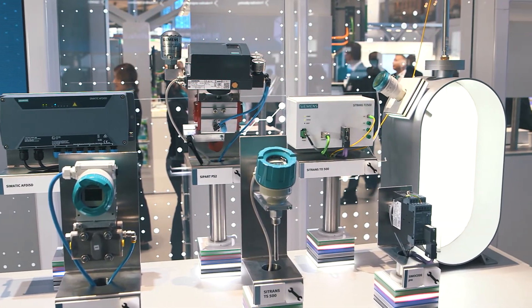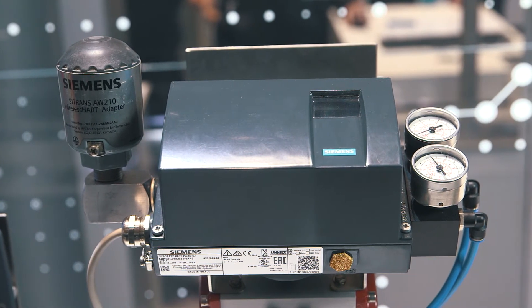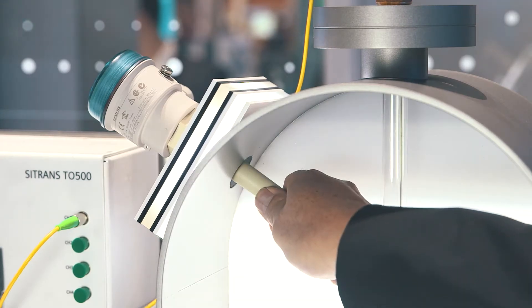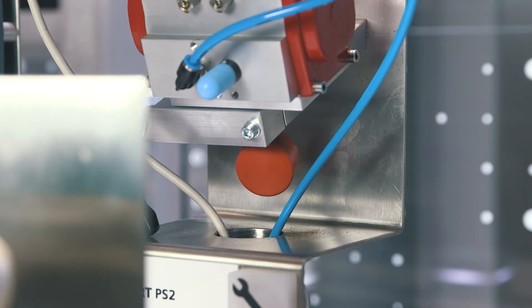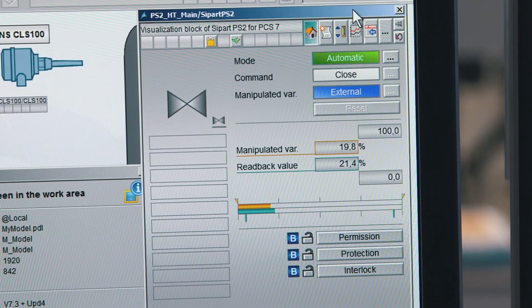Let's go from the cloud back to the field and focus on the plant operator. How can optimal transparency on the status of the valves in the operator's plant be achieved while using the diverse functions of our SIPART PS2 positioner? The key word is wireless industrial communication. The position of the valve and the SIPART PS2 diagnostic information are transferred to the SIMATIC PCS7 control system via wireless communication with the WirelessHART industrial standard.